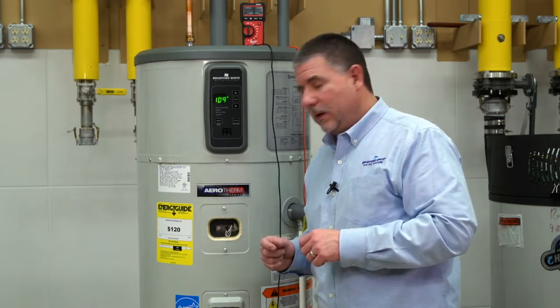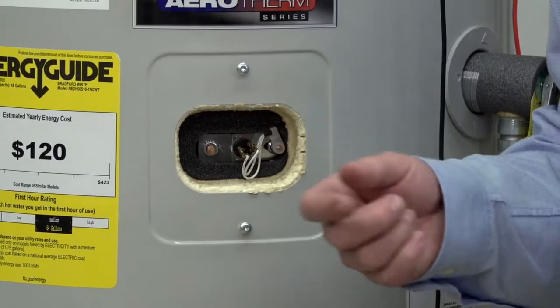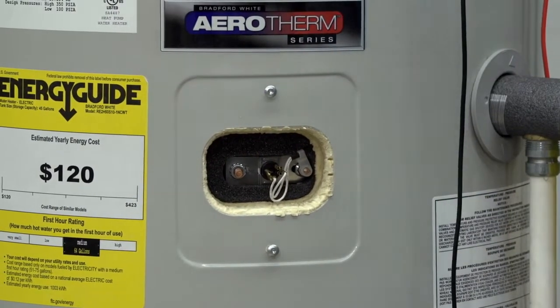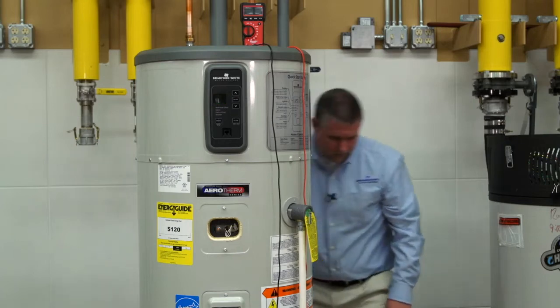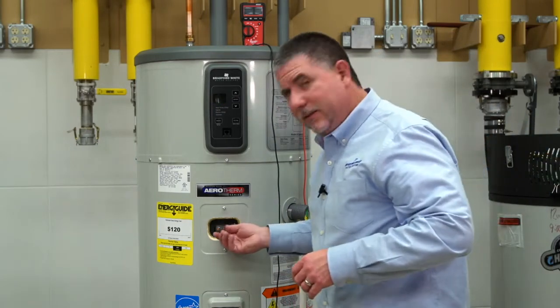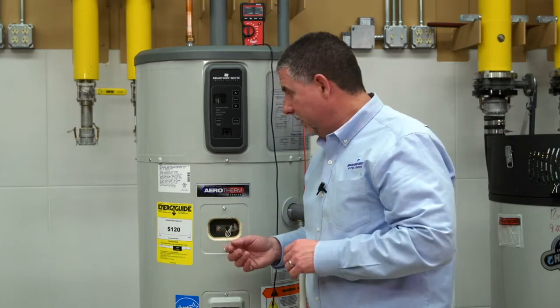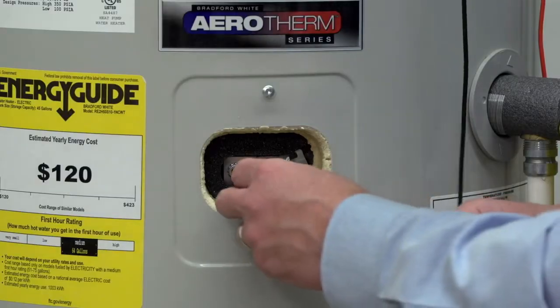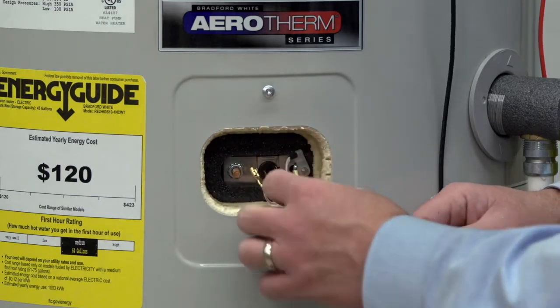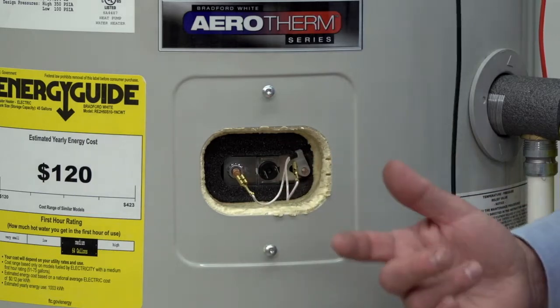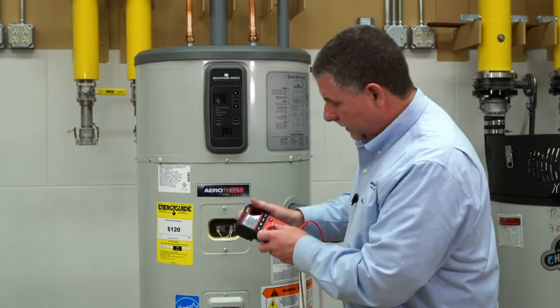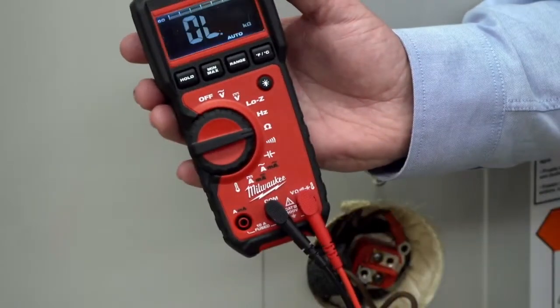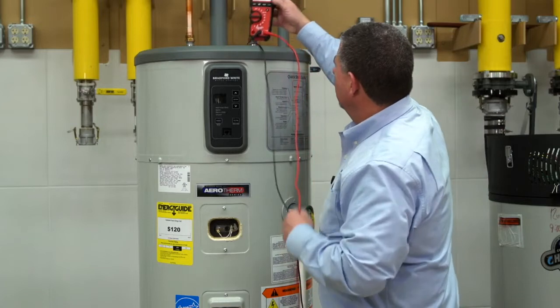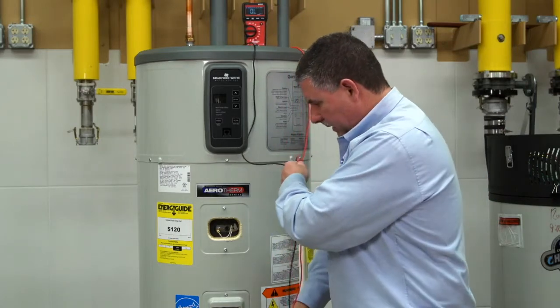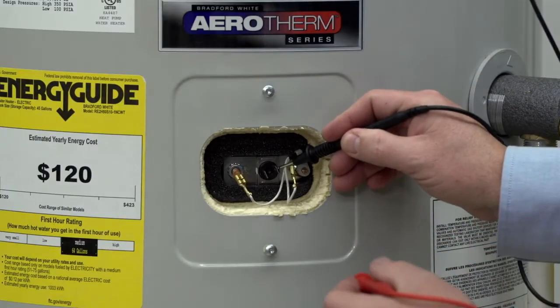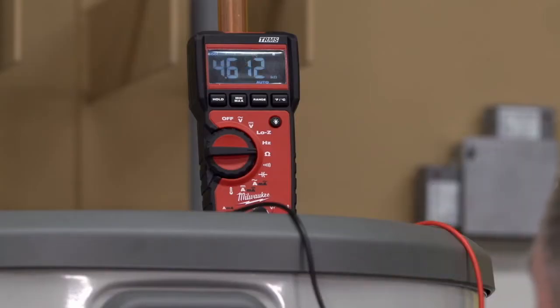So now to test the T2, we're going to actually remove the white wires. So for this, I'm going to power the control off. I'm going to go behind the water heater, turn it off. Okay, so power is off. And this is a resistance-based circuit. There's no electricity involved here, but we do want to isolate the component. So I'm going to take the white wires loose. And what that's exposed is my T2 sensor. I'll use my multimeter. I'm going to adjust that to a resistance setting. So from my off to my omega sign. Okay. And we're going to measure resistance of the T2 sensor. So going from one terminal to the other terminal, I should get a resistance value.